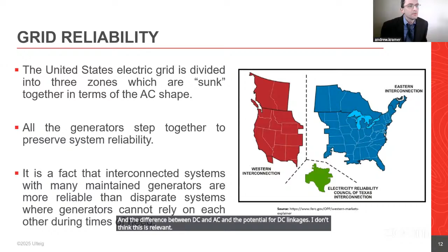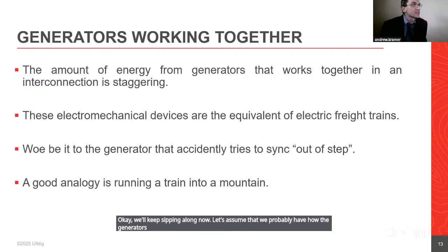Okay, we'll keep skipping along then. Let's assume that we probably have how the generators work together for frequency, and we can go into tie line bias control, which is potentially something people don't have at that point. So the control mechanism for the United States to maintain frequency is what we call tie line bias control. And the methodology of measuring how healthy the grid is, is called area control error, also known as ACE.